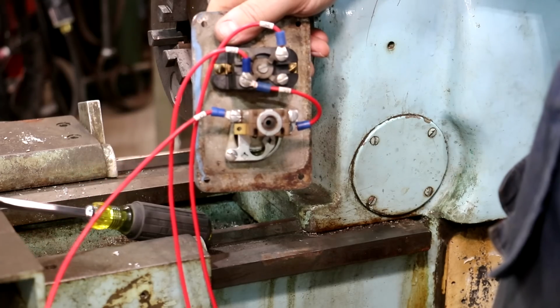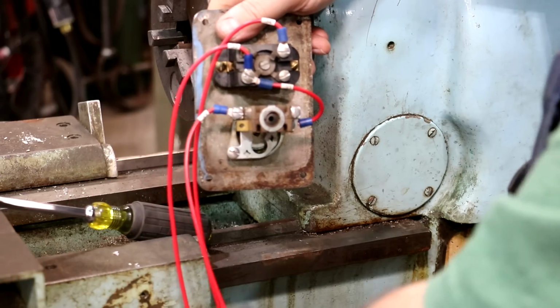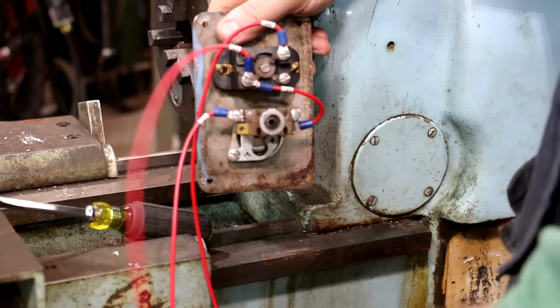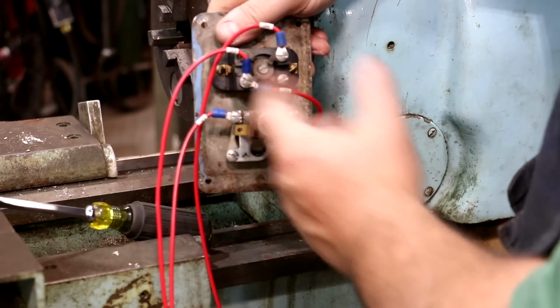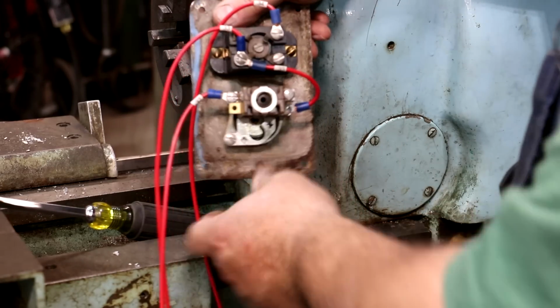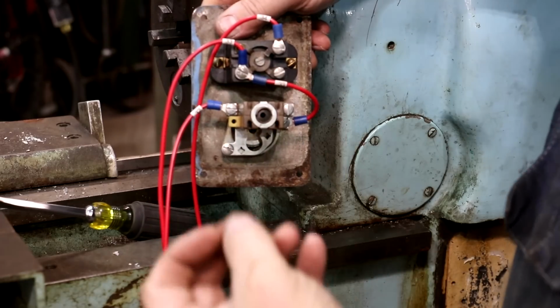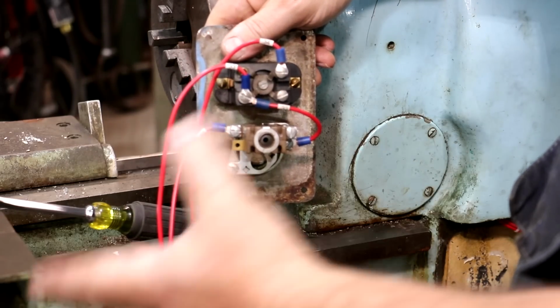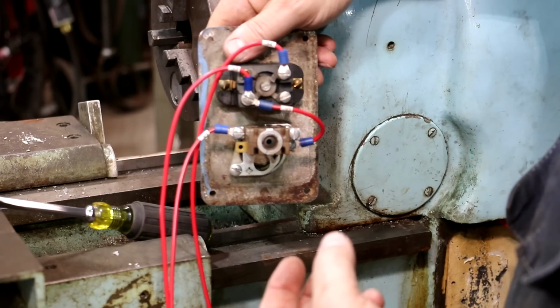It energizes the coil, and as soon as it's energized, it's sending the power that was coming in on 33 back through. So once we release that switch, the power's in here, the motor starter is engaged, the coil is on, and it's going to stay on until the power drops.